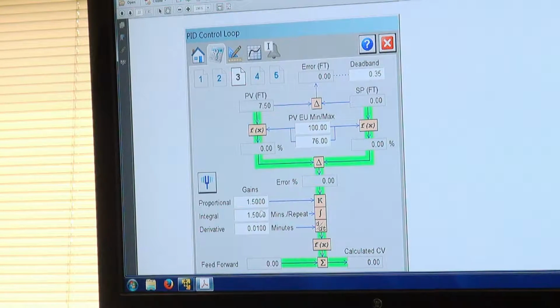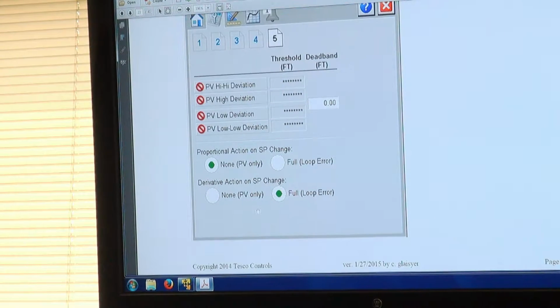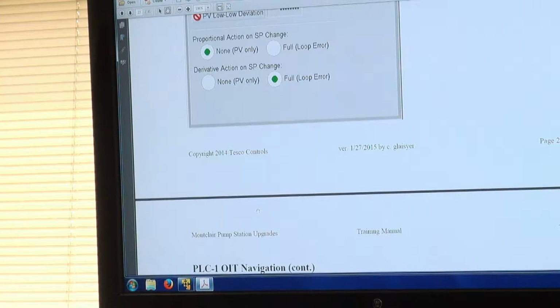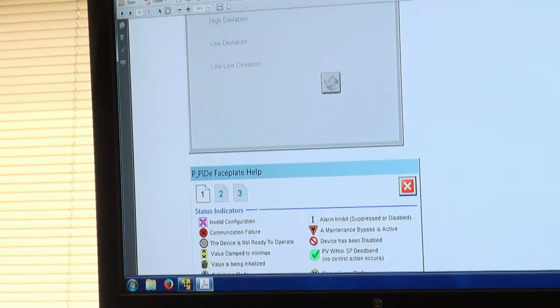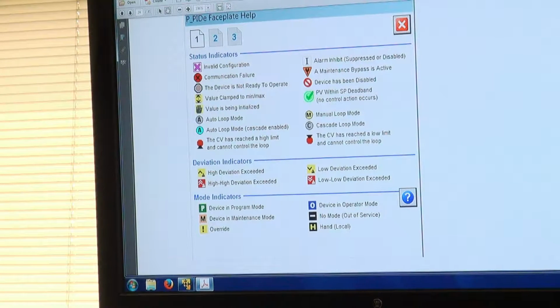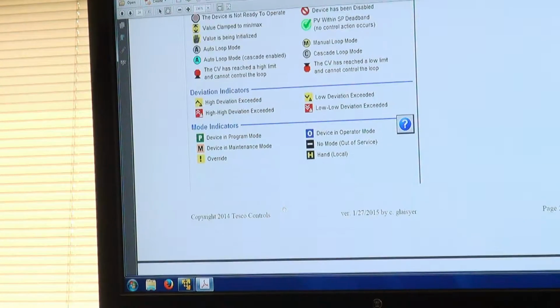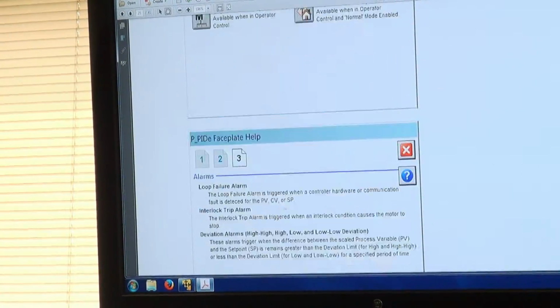You go up a hill, all of a sudden you realize you got to press a little gas, and then when you go down, you got to let off because you're trying to maintain. Your cruise control works this way. Our pumps work this way. We've been pretty consistent, so there shouldn't be any need to change this, but if ever you do, this would be where you would make it. Again, I displayed all the screens for you, but that was the big one. If there's ever any question that you have on that, there's your help menu, which is available on every object.